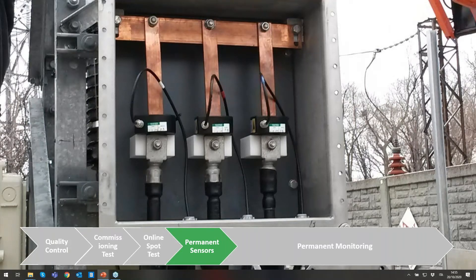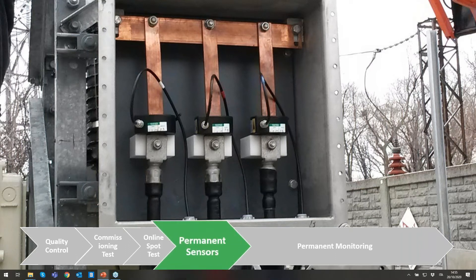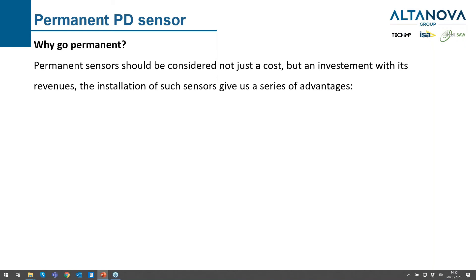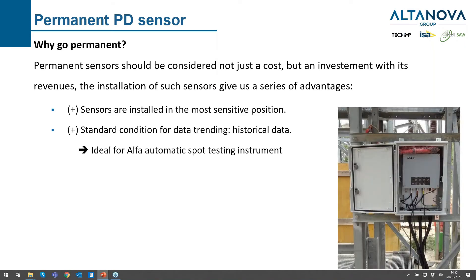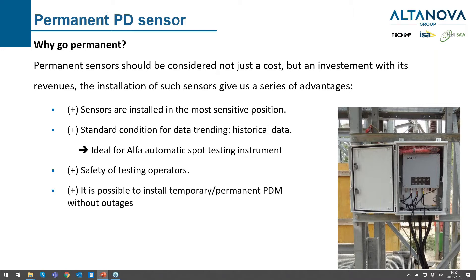A permanent sensor can be a very good choice when installing a new asset, especially because it's an investment with many advantages. We have the possibility to install the sensor in the most sensitive position. We also have standardized testing conditions — if you want to compare data from different sessions, for example one from 2008 with one from 2021, in some cases we have data more than 10 years old and we keep adding new data on the same sensor for comparison.